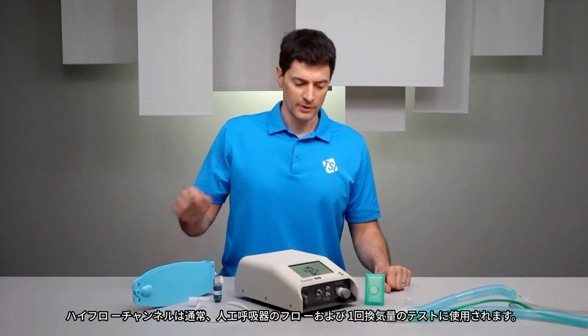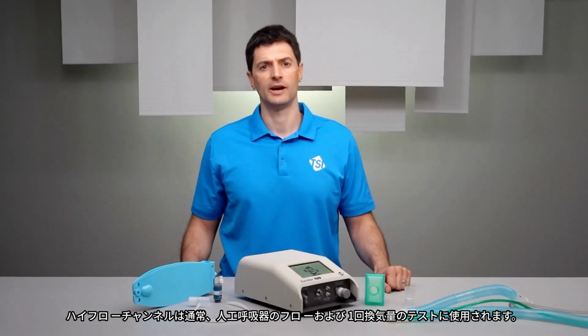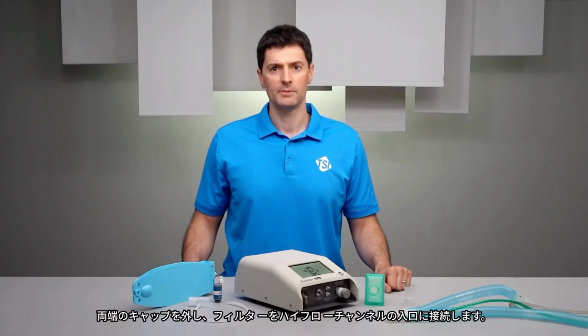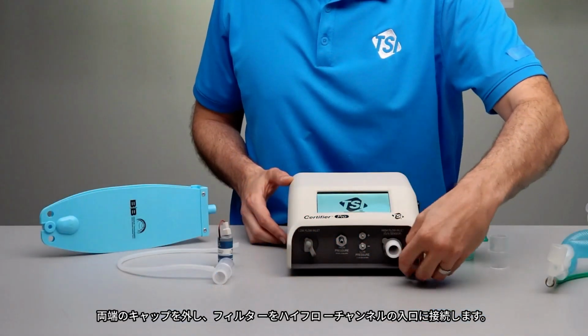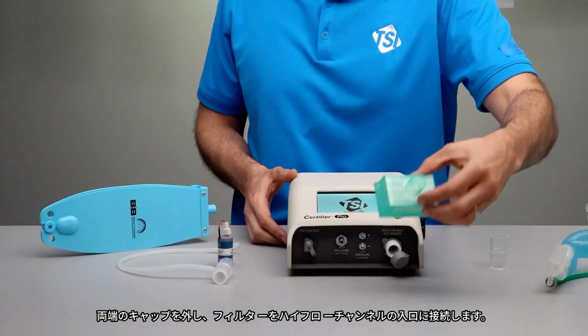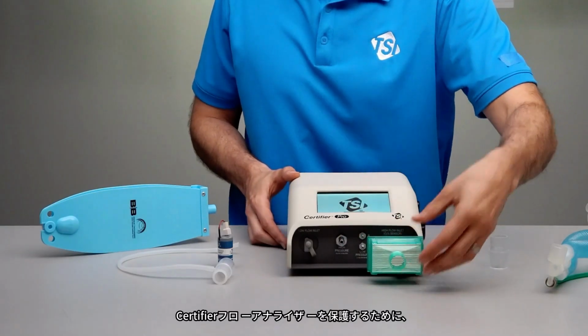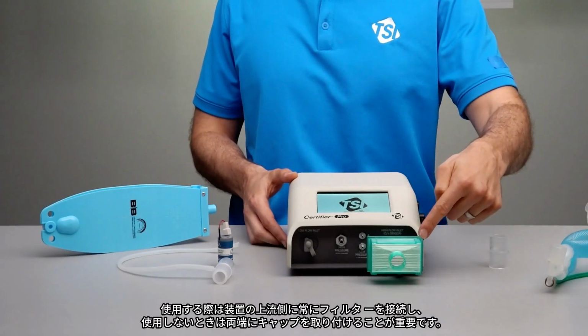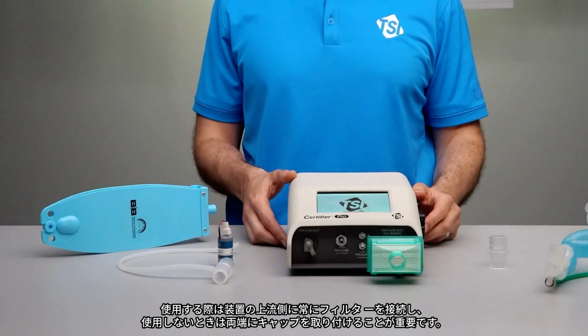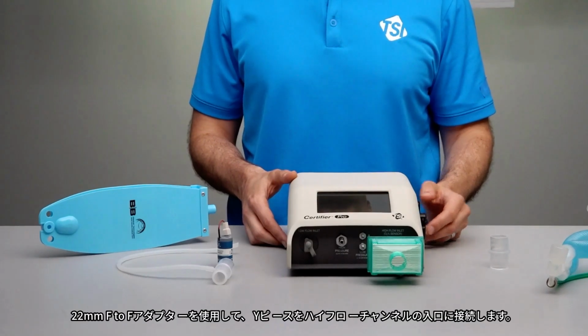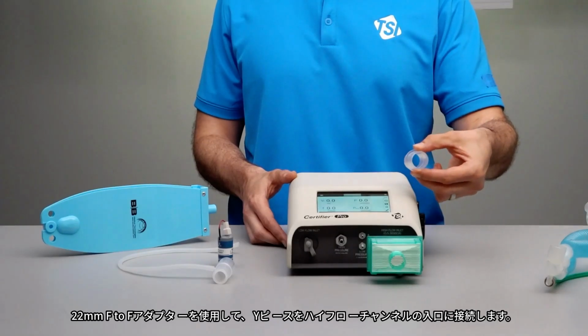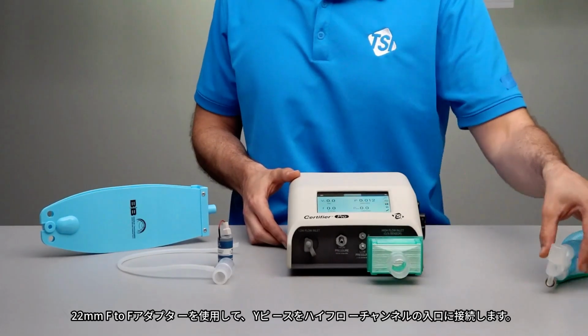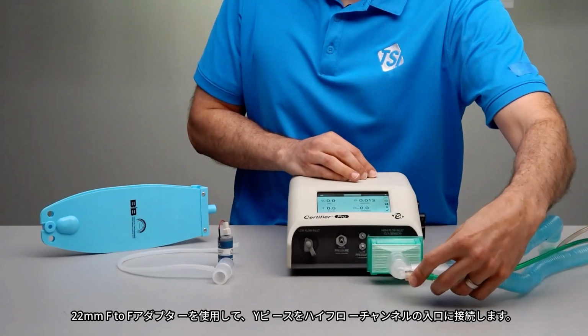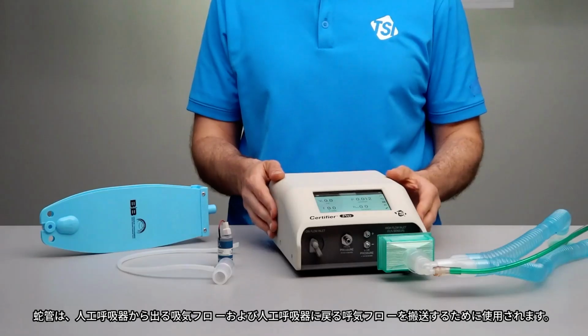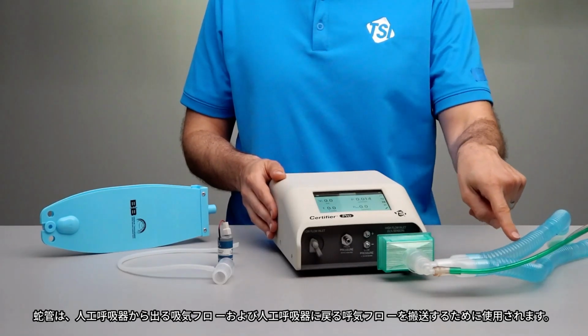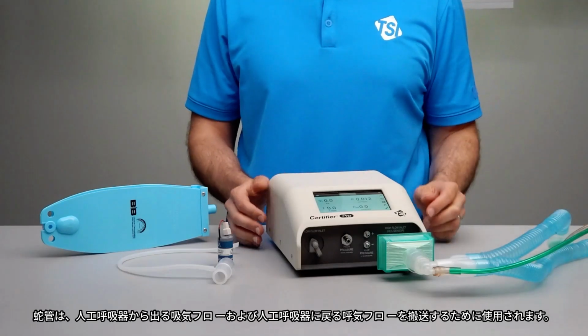The high flow channel is typically used for testing flows and tidal volumes from ventilators. Uncap the ends and connect the filter to the inlet of the high flow channel. To protect your Certifier flow analyzer, it's important to always operate with a filter upstream of the instrument and to cap the ends when not in use. Using the 22mm female-to-female adapter, connect the Y fitting to the inlet of the high flow channel. Corrugated tubing is used to carry inspiratory and expiratory flows from and back to the ventilator.